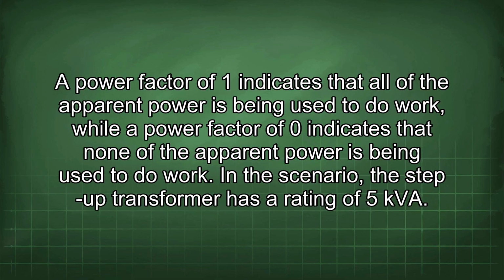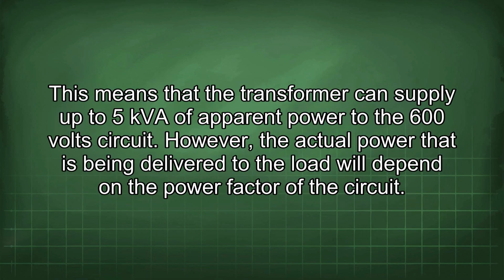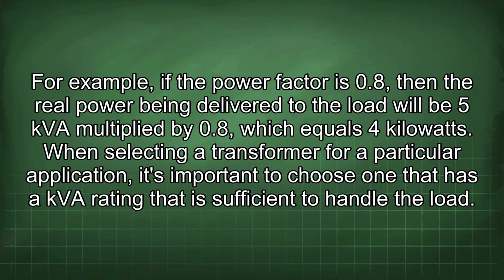A power factor of 1 indicates that all of the apparent power is being used to do work, while a power factor of 0 indicates that none of the apparent power is being used to do work. In this scenario, the step-up transformer has a rating of 5 kVA. This means that the transformer can supply up to 5 kVA of apparent power to the 600-volt circuit. However, the actual power that is being delivered to the load will depend on the power factor of the circuit. For example, if the power factor is 0.8, then the real power being delivered to the load will be 5 kVA multiplied by 0.8, which equals 4 kilowatts.